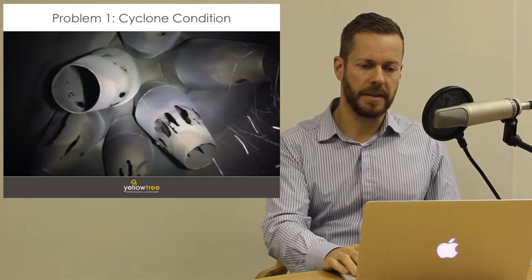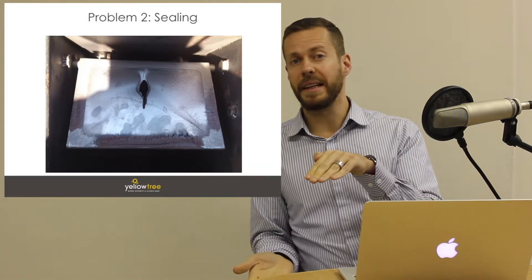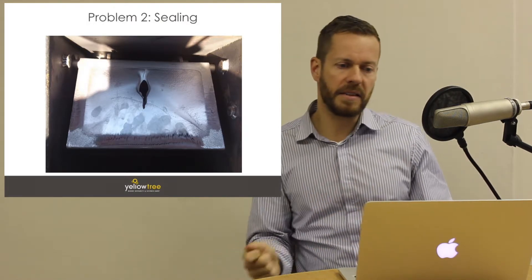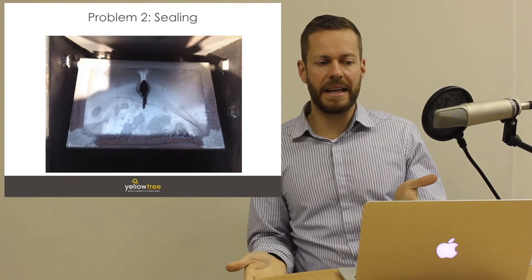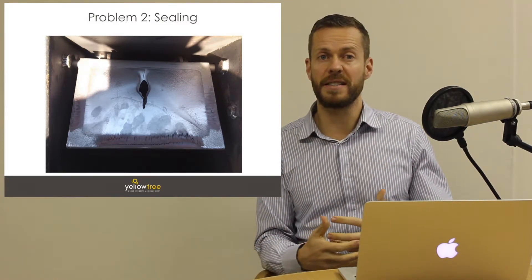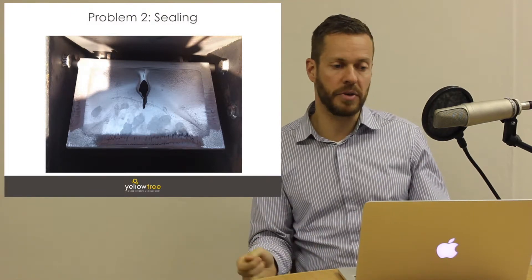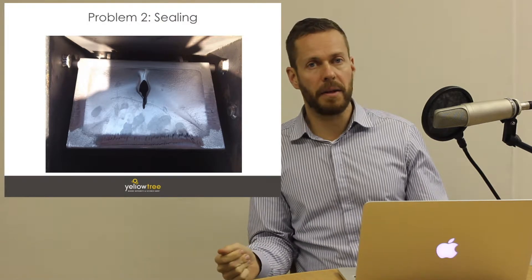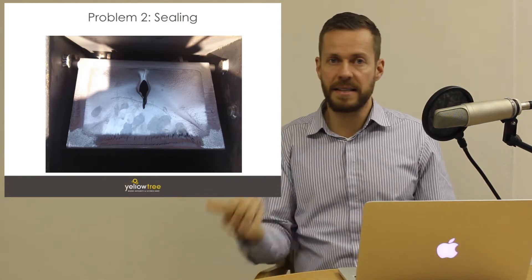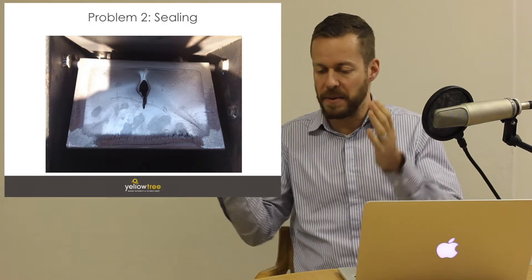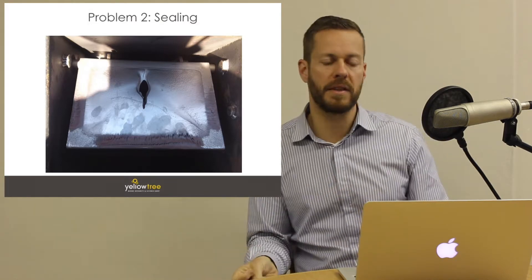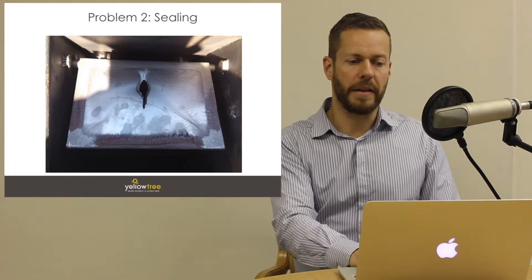The second problem with multicyclones is that the two sealing flaps at the bottom are also subject to abrasive particulate matter that wears through them. This photograph shows a hole in one of those sealing flaps — not caused by any mechanical force, but by erosion, worn away like sand dunes. As soon as there's a hole in the sealing flap at the bottom, air will be sucked in because the ID fan is downstream.